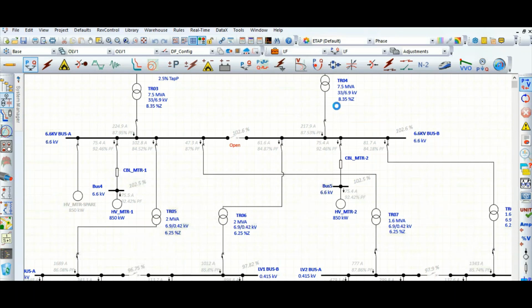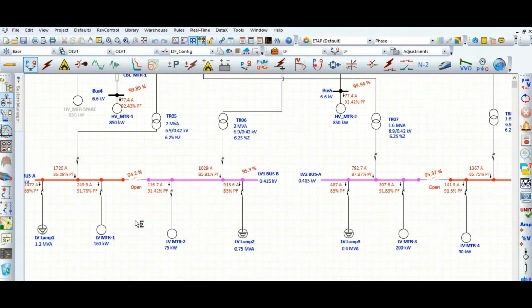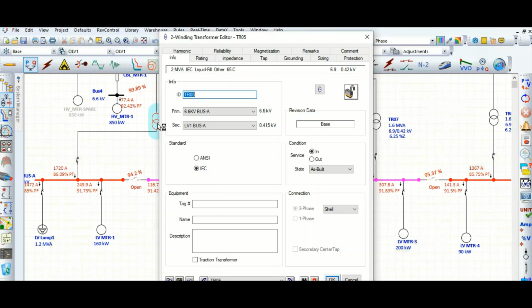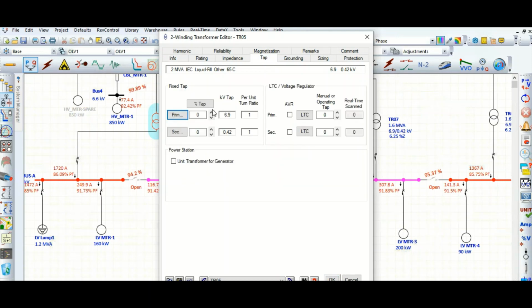So now we can see this voltage profile is improved from 97% to 99.99% and bus B 100%. But for the downstream, you can see this downstream bus voltage is 94.2%, here 95.3%. So let's change the tap here. In this case we need to decrease the tap, minus 2.5%.